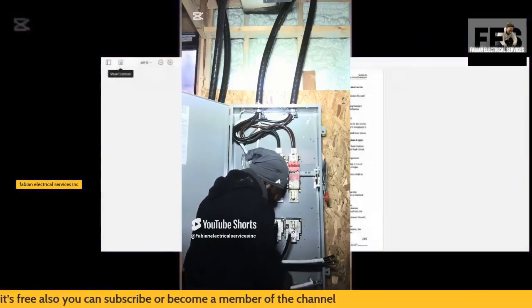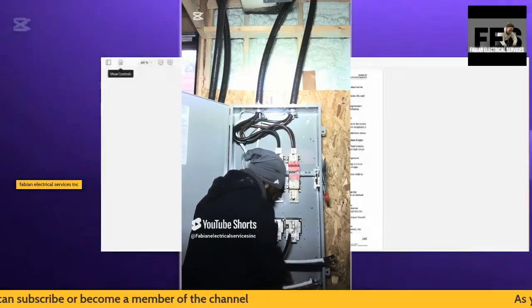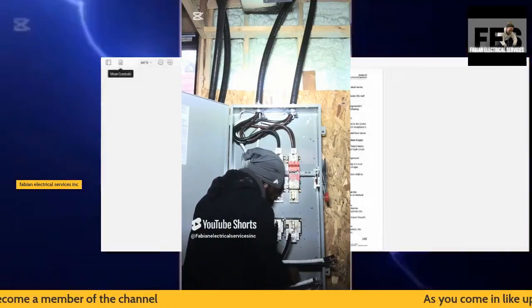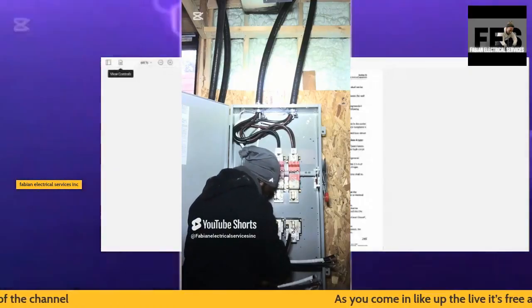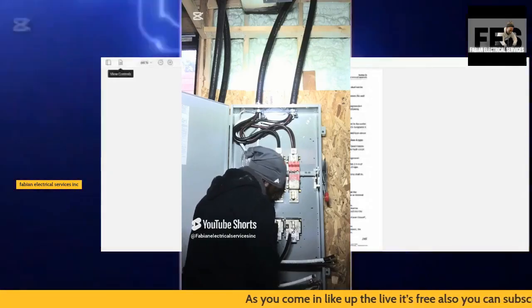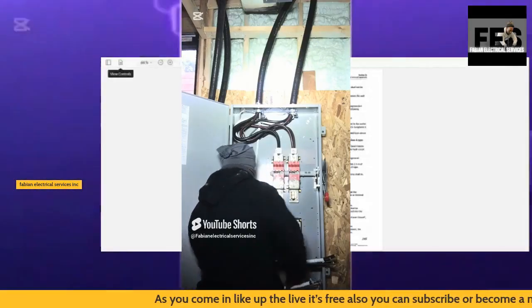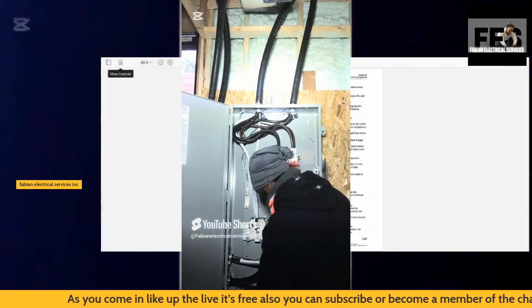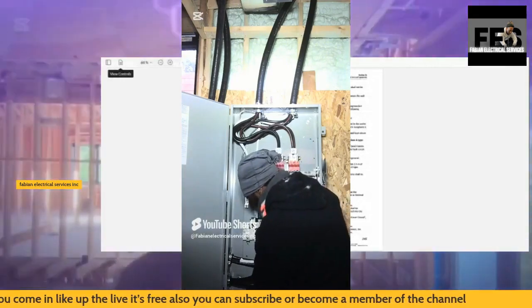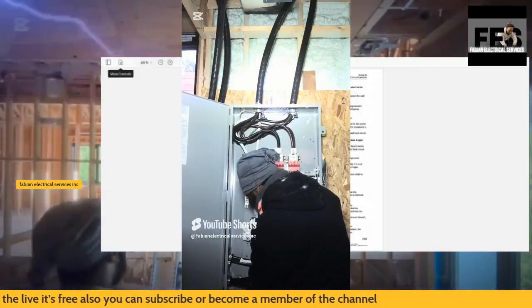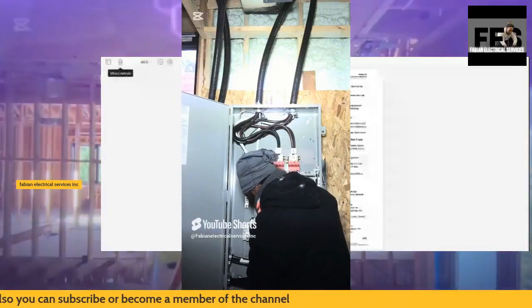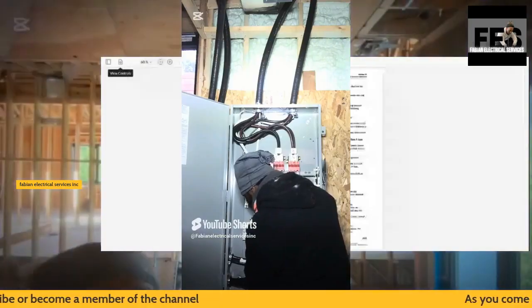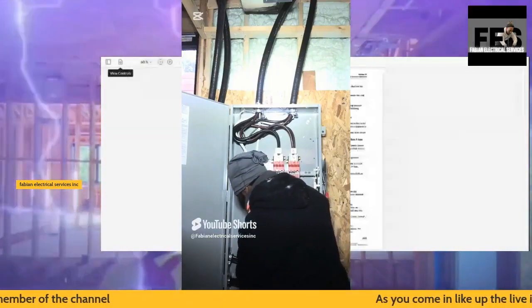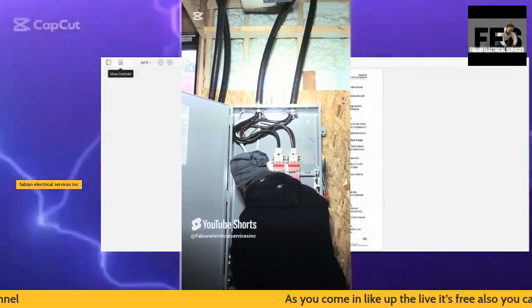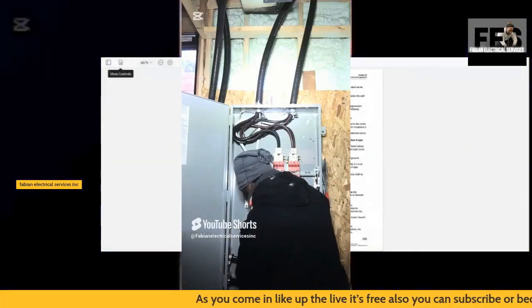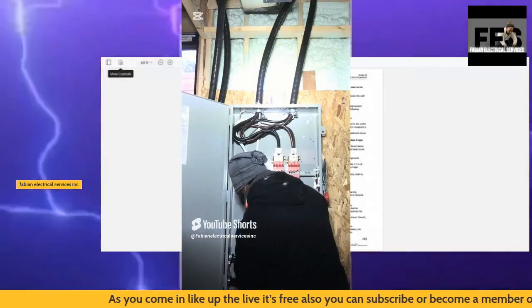Also, you will see me have the cables wired up into the lugs, the main disconnect, a 400 amp disconnect service that I have here that I'm working with, and the cable that I used was 250 kcmil parallel runs. And again, you'll see all my ground bushings and everything is grounding the ground wire off, and it's going back to the main ground on the panel.